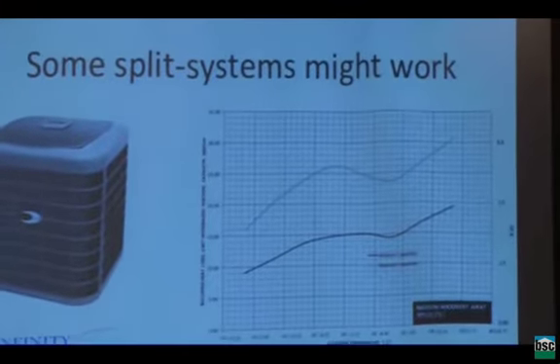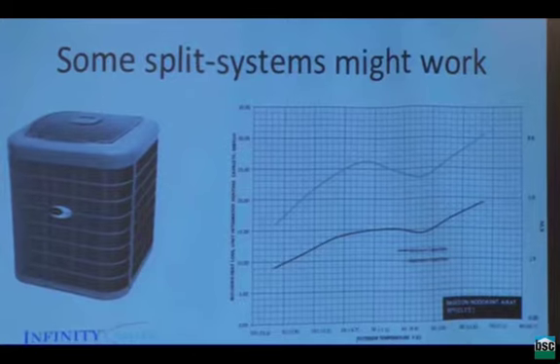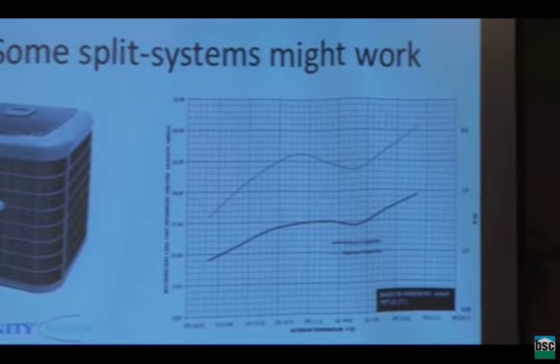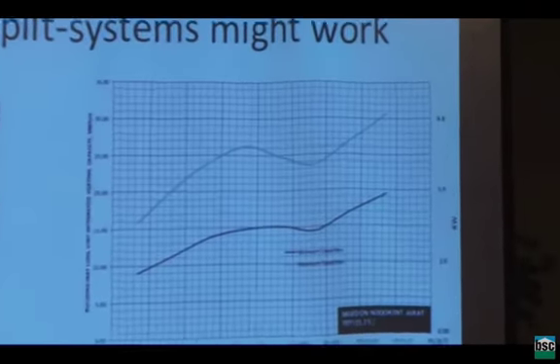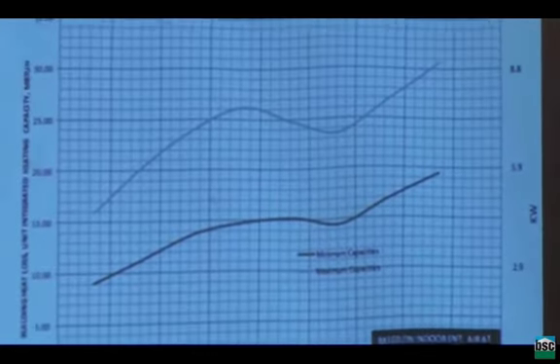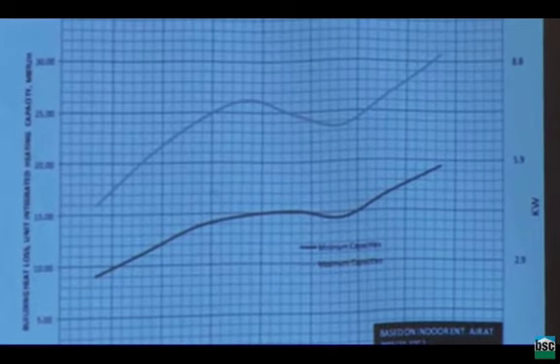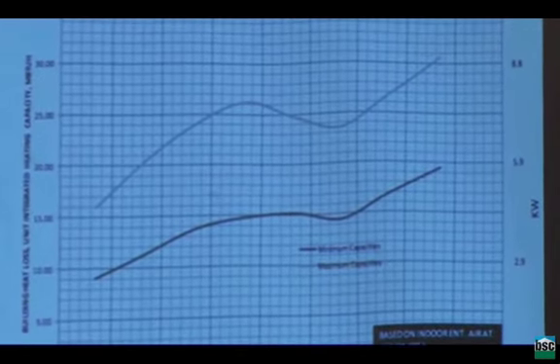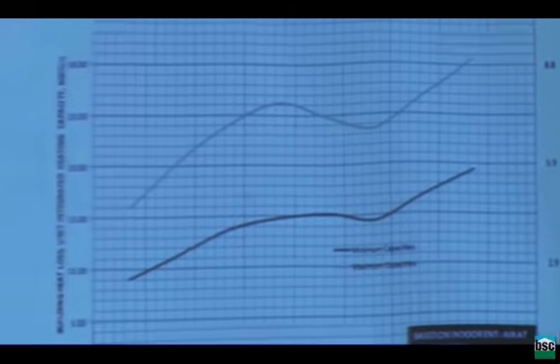Okay, so how could I fix this problem? Well, the obvious thing is don't use a single-speed air conditioning system as a heat pump. Use a 2-speed or a variable speed. Now here the variable speed, unlike in the furnace market, really can make a difference, because I can now say when it is cold outside, 20, 10, 0, I can run either the high speed stage or run the compressor as fast as possible.